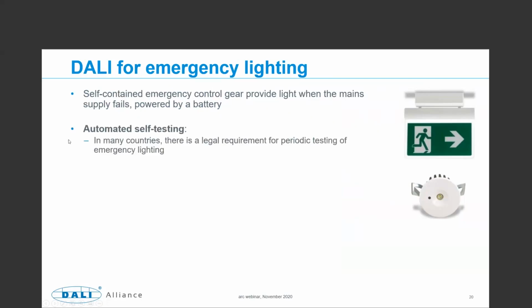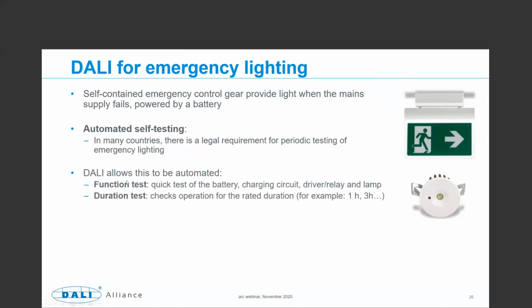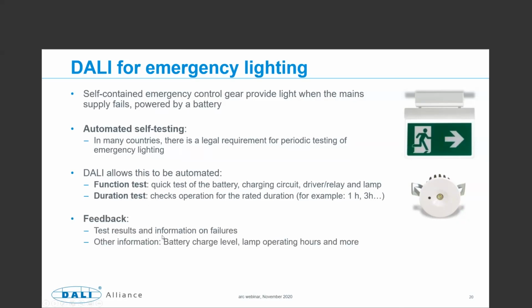Now, this allows automated self-testing, and in many countries there is a legal requirement for periodic testing. DALI allows the two types of tests to be automated: the function test, which is a quick test of the battery, charging circuit, the driver and relay, and the lamp, and the much longer duration test, which checks for operation of the lamp from the battery for the rated duration. And of course, you get the feedback of all the test results and information on failures. Other information you can get includes the battery charge level, the lamp operating hours, and more.